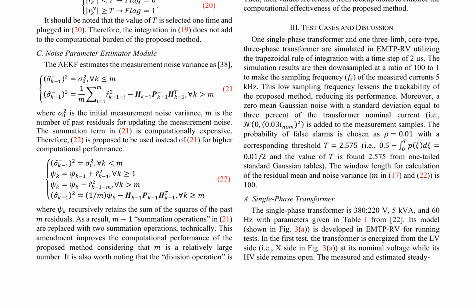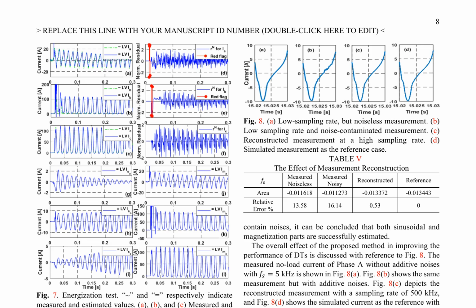The AEKF method is applied to a single-phase transformer and a 3-limb, core-type, 3-phase transformer, and simulation results show that it can accurately estimate the magnetic flux linkage even in the presence of noise and nonlinearity. The estimated currents closely match the measured currents, and the errors in estimation are negligible. The paper also discusses a recursive method for developing measurement integrity verification suitable for transformer currents in hardware-in-the-loop, HIL, digital twins, DTs.